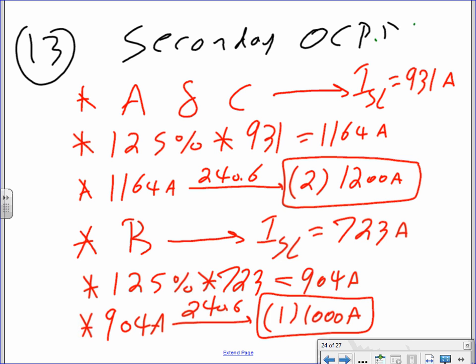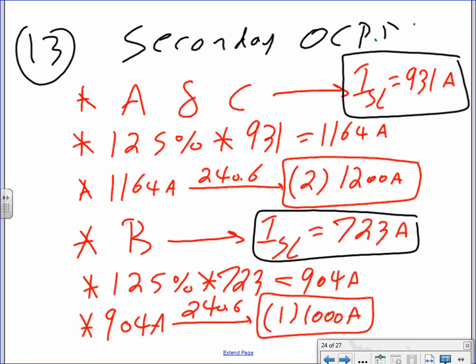I cannot emphasize, Adam, that these are the key points for the solution: to identify the current. The minute that you find the primary and the secondary line current for phase A, B, and C, then you start just multiplying them by the multipliers. A lot of mistakes, guys, is people put this one here and that one there. The steps of multiplication, please write yourself a note. Bring your code book, write in it.